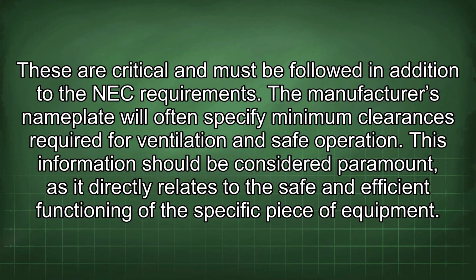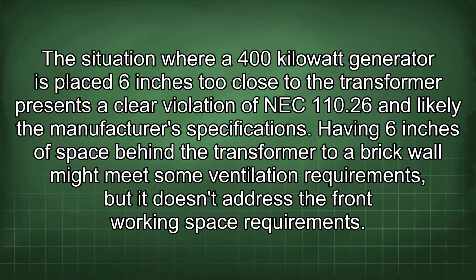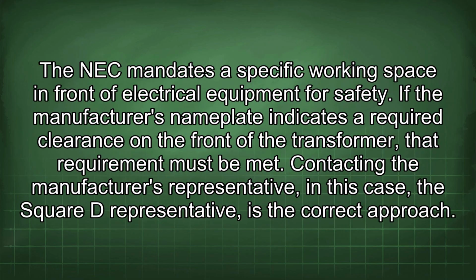The situation where a 400 kilowatt generator is placed 6 inches too close to the transformer presents a clear violation of NEC 110.26 and likely the manufacturer's specifications. Having 6 inches of space behind the transformer to a brick wall might meet some ventilation requirements, but it doesn't address the front working space requirements. The NEC mandates a specific working space in front of electrical equipment for safety. If the manufacturer's nameplate indicates a required clearance on the front of the transformer, that requirement must be met.